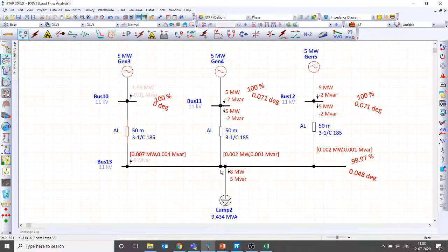Since the demand is only 8 megawatt, after a small loss, this generator is consuming 2 megawatt. This generator is consuming 2 megawatt. This is not really a right scenario. It has to be shared equally. But this is a drawback of the slack bus concept.